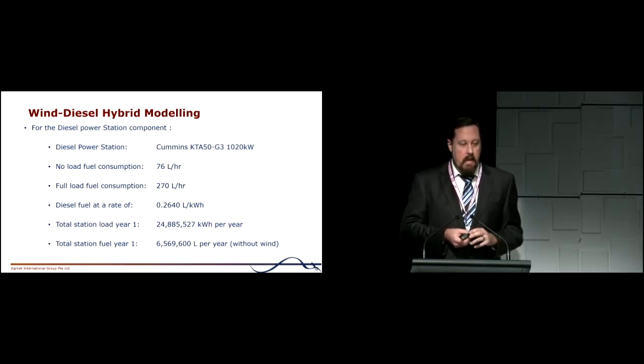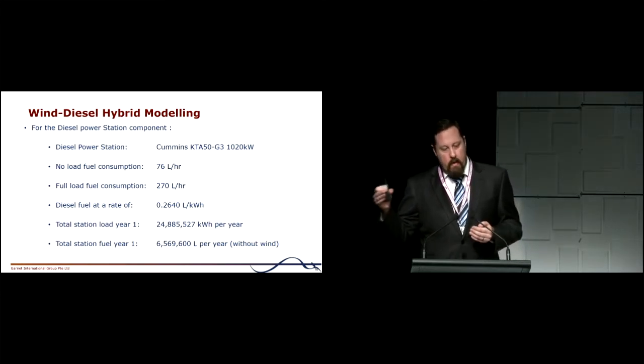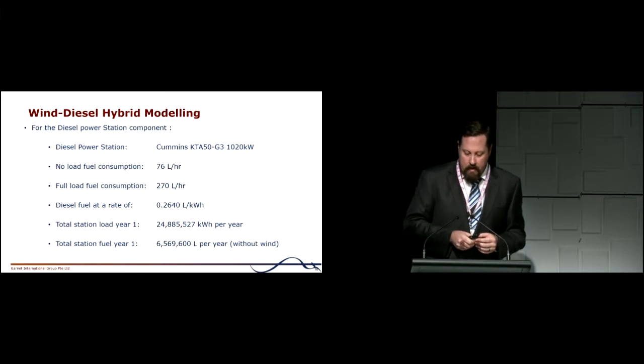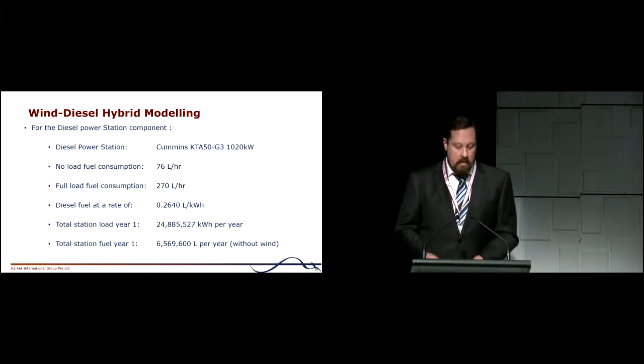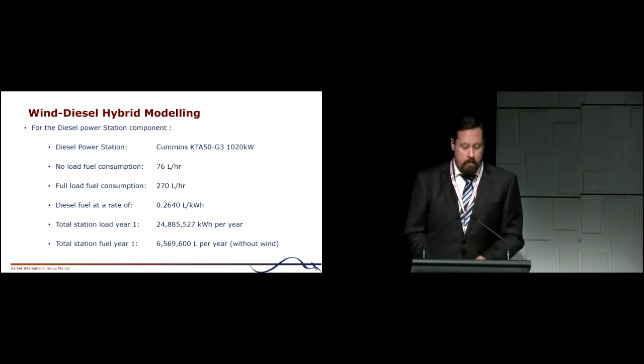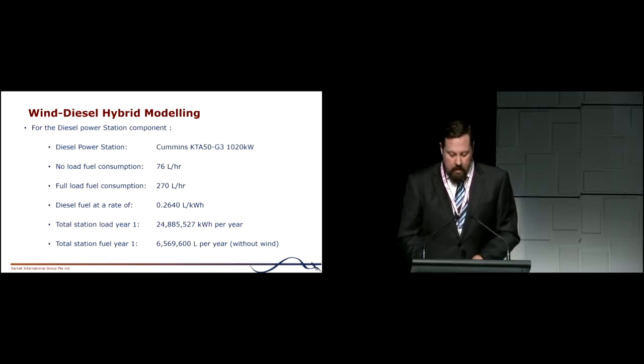We know that the renewable energy can offset diesel consumption. It can offset it to a point. There are a few more percent to chase after that. That's what we're after at the moment. So the full load fuel consumption is 270 litres an hour per generator for the units, and a diesel conversion rate of 2.6 kilowatt hours per litre.